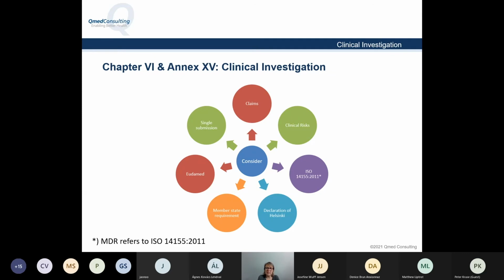Even though the Medical Device Directive at that time was meant to be European legislation, when it was incorporated into the national law text, a few changes were made. There are specific requirements for Italy, Spain, and all the other countries, and you have to do a little detective work to find out what the requirements are.